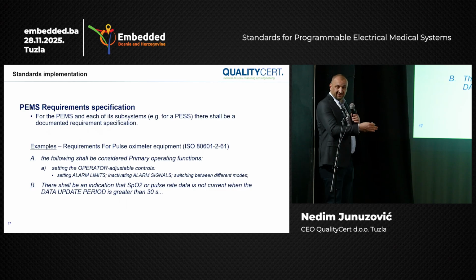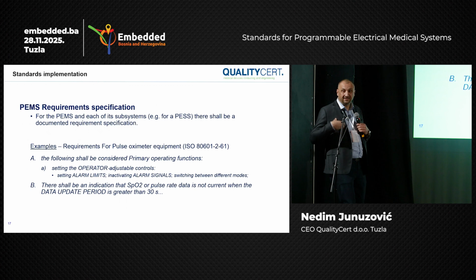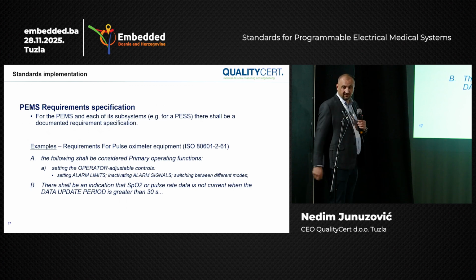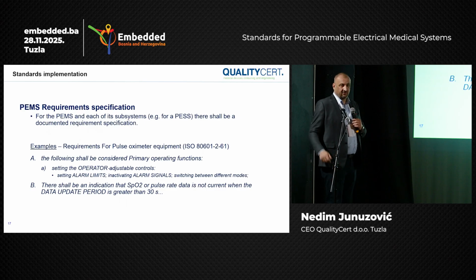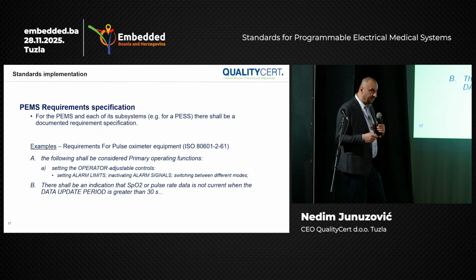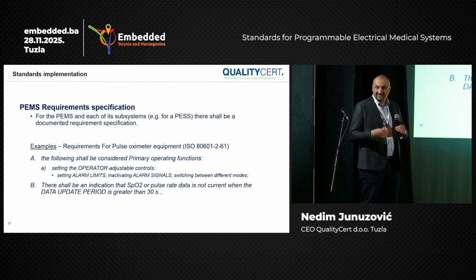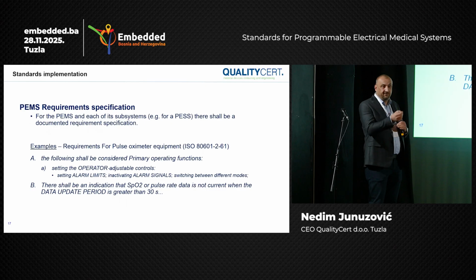I was reading fast, but actually it says there shall be indication. So you have to provide indication for the user in cases of extended data collection period. So as an engineer, you ask: what is the indication? Is it auditory? Is it visual? What indication do I have to provide, and how do I collect and ensure 30 seconds of data collection and so on. With infants, it's even a shorter period.